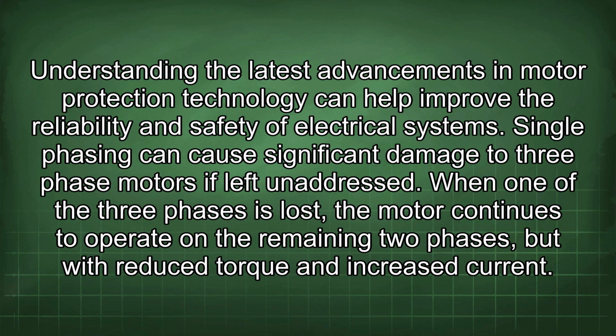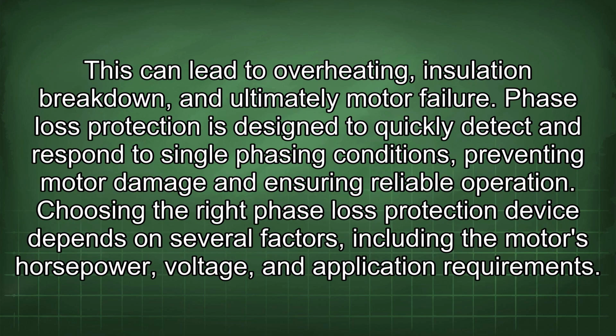Single phasing can cause significant damage to three-phase motors if left unaddressed. When one of the three phases is lost, the motor continues to operate on the remaining two phases but with reduced torque and increased current. This can lead to overheating, insulation breakdown, and ultimately motor failure.